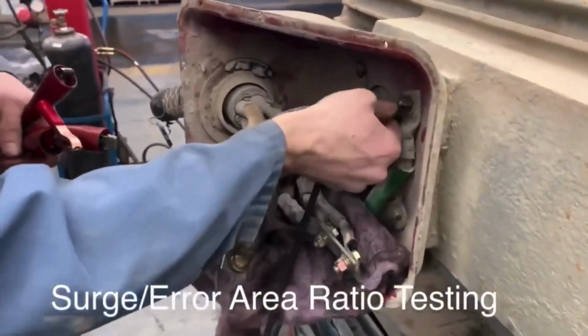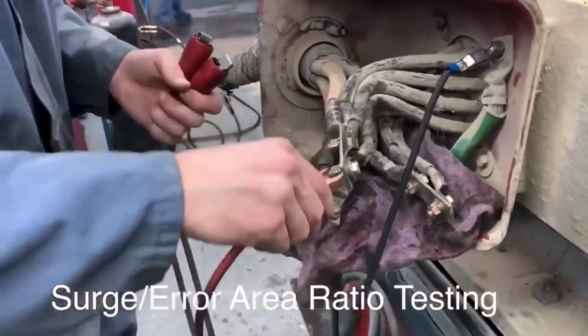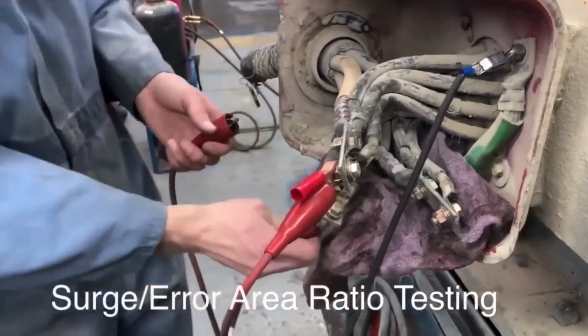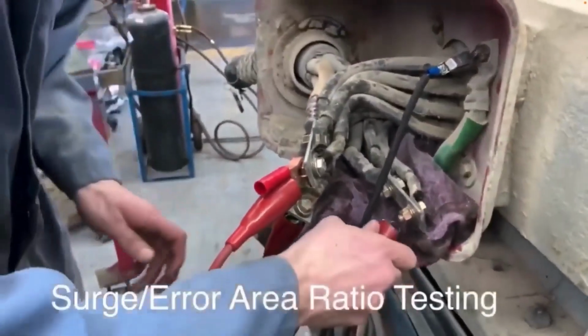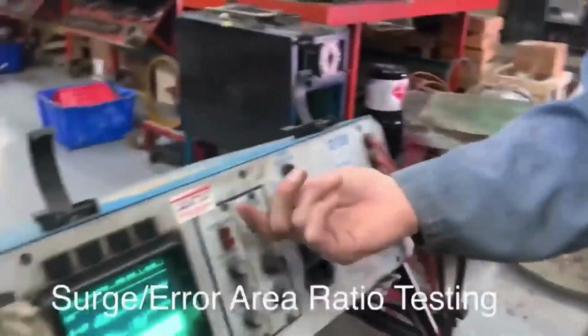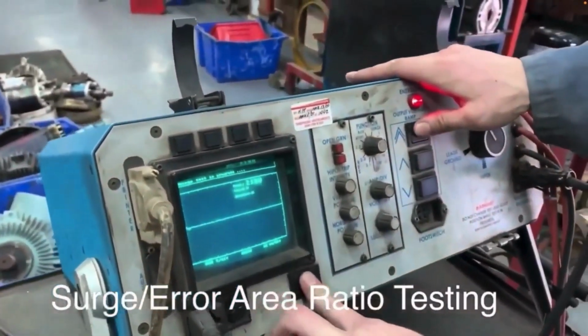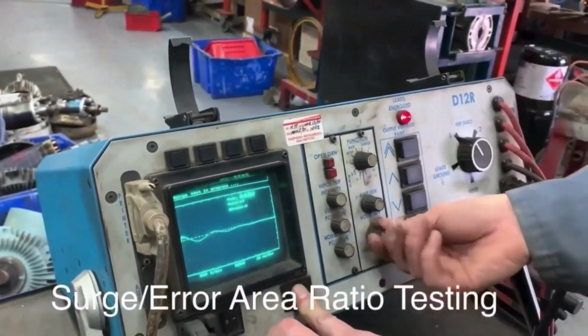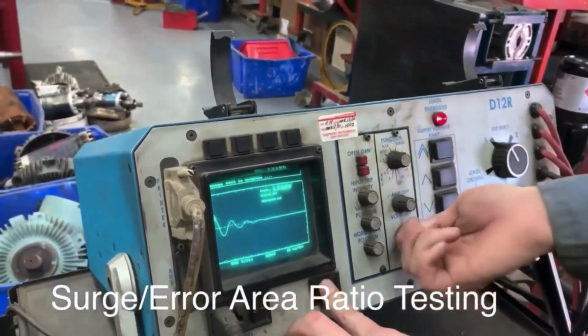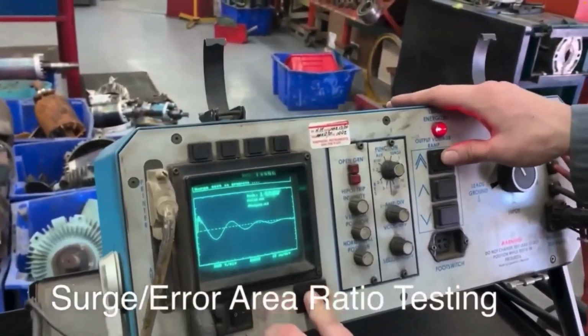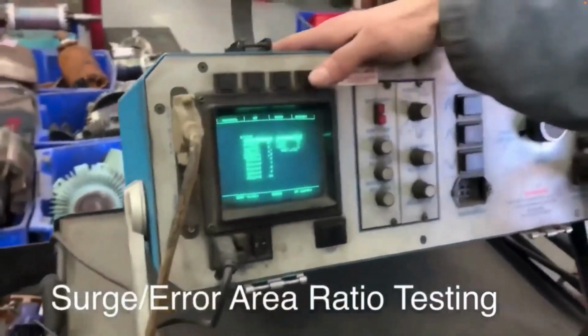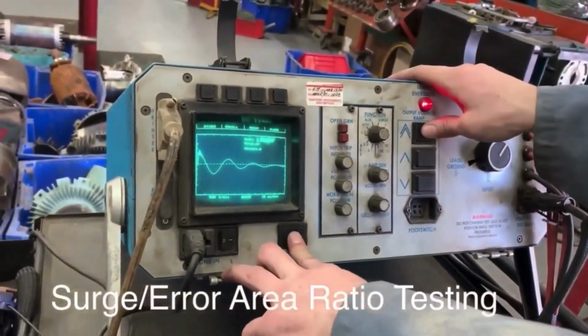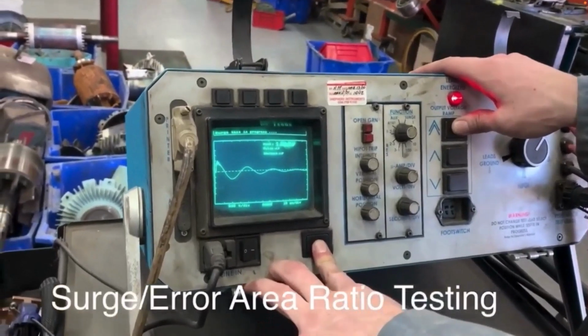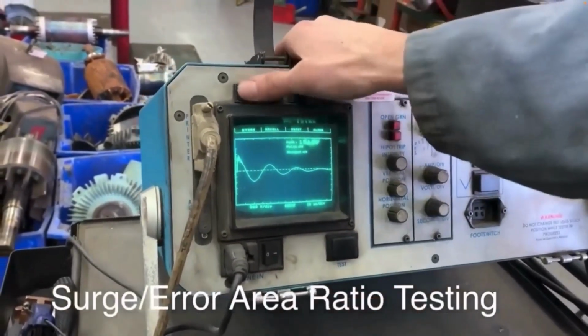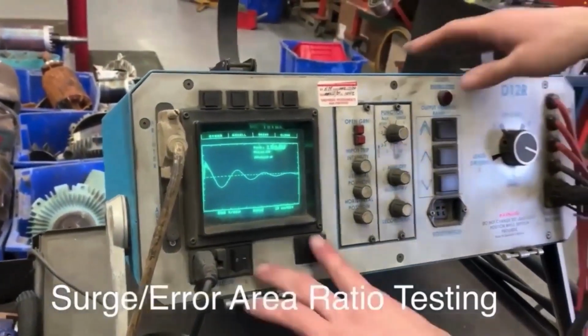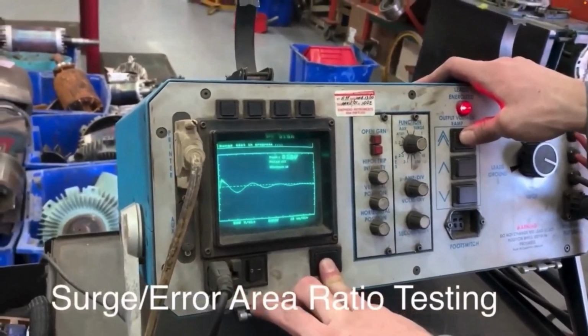During a surge test, a surge capacitor connected in parallel to the winding to be tested is discharged suddenly. A sinusoidal damped oscillation is created in the oscillating circuit between the testing device and the windings, and this oscillation has certain characteristics. A test lead switching matrix in the surge tester connects the output leads to provide a complete electrical circuit. For a three-phase stator, this is usually between two phases. One phase is energized, the other phase or other two phases are grounded. The result of the test is displayed on the screen.